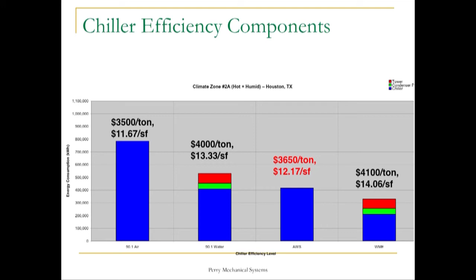So some of the things we've talked about already as far as water-cooled machines go: you're going to have a higher maintenance cost that you have to deal with and more qualified technicians. But most of our institutional buildings that are dealing with these size systems can deal with that. You're dealing with higher water treatment costs. And this amazed me. When somebody told me these numbers, I had to go verify them myself. I checked it out two different ways, and it was true. On a 500-ton system, say a middle school, the cooling towers, which are what cool the chillers outside, evaporate 13,500 gallons of water a day. That's a swimming pool. Every day they evaporate.